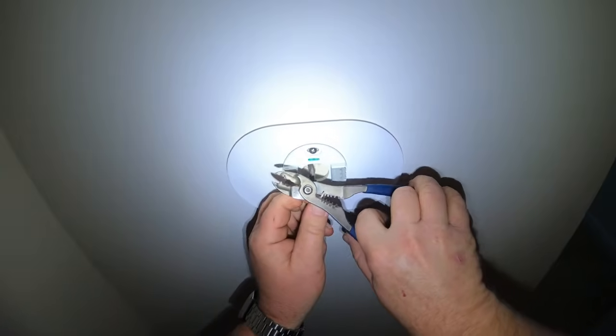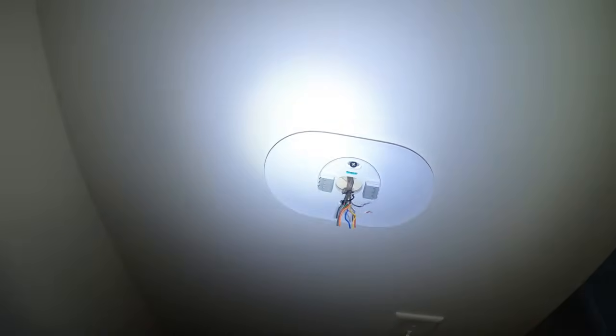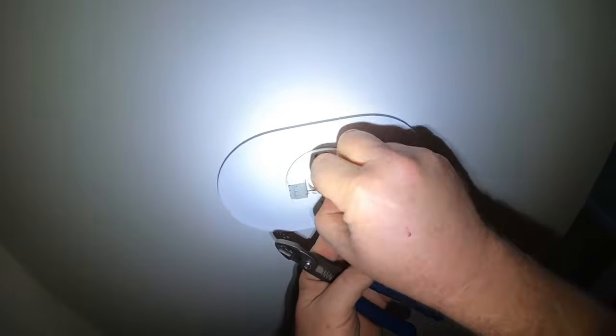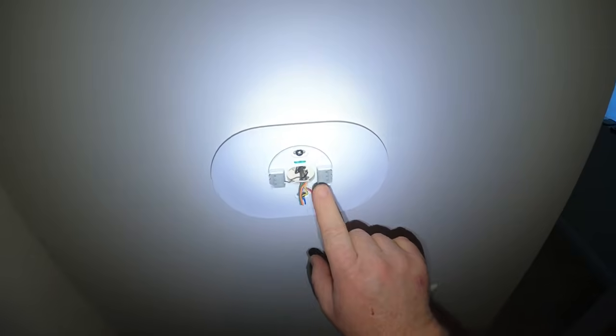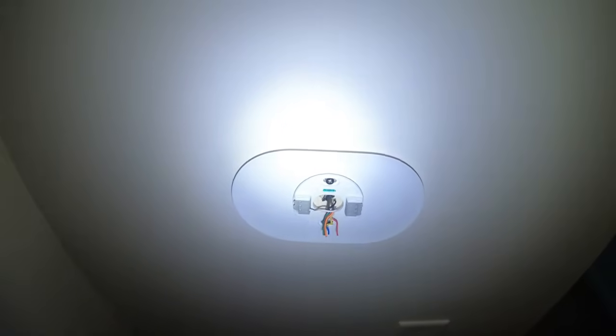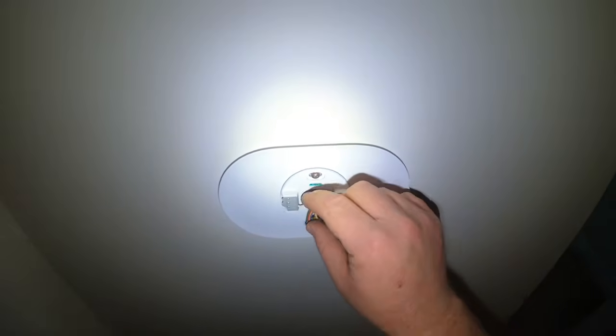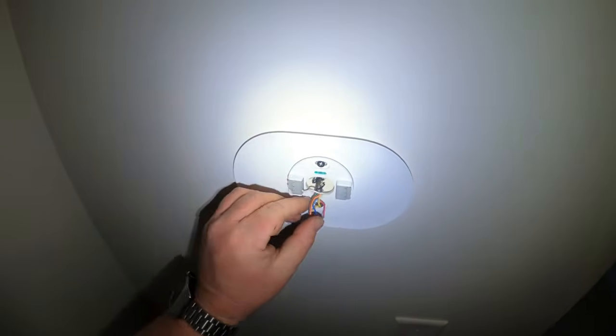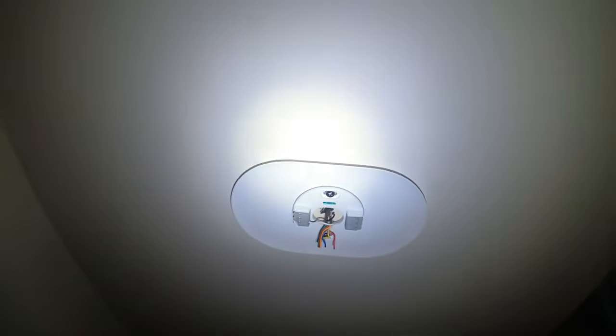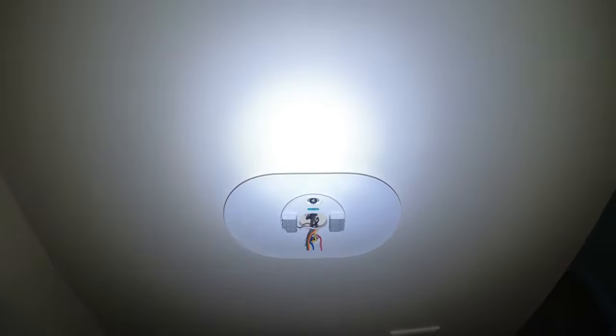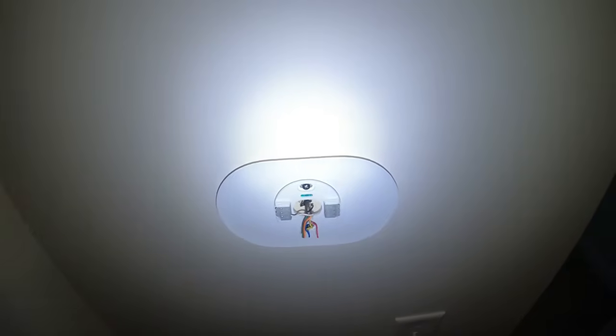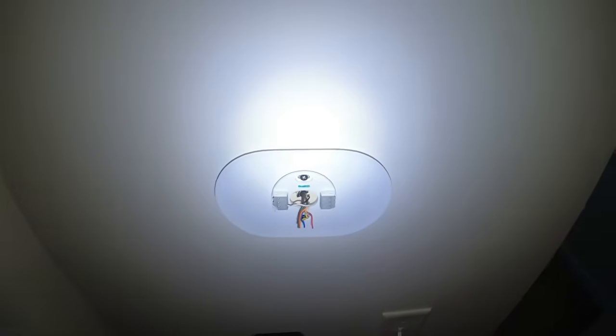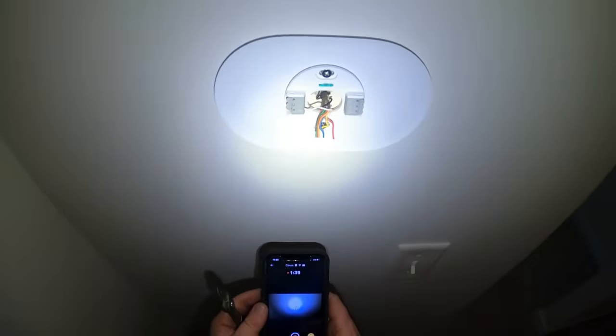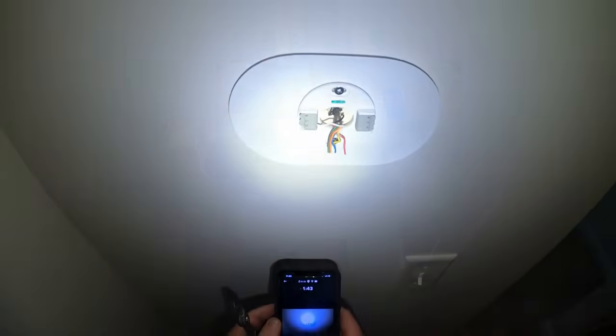So anyway, you guys have installed thermostats before. I'm not going to make a whole 5-minute section in this video about doing that, but I've got a G, an R, an OB terminal, a W, a C, and a Y on this, so I should be able to set this up for dual fuel, or at least set it up where it'll run properly. Then I'll let the control board, the zone board upstairs, control the staging from the heat pump to the furnace, and we'll just do a simple temperature lockout on it, and that typically works perfectly fine with a single stage furnace and a single stage heat pump. If I had multiple stages, like a 2-stage outdoor unit and a 2-stage or 3-stage indoor unit, we would do something a little different. All right, I'll be back when we get ready to set that board up.